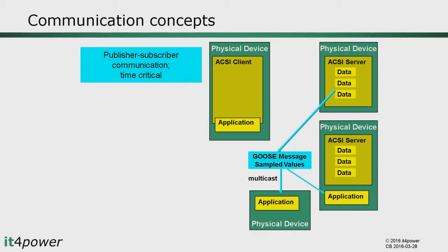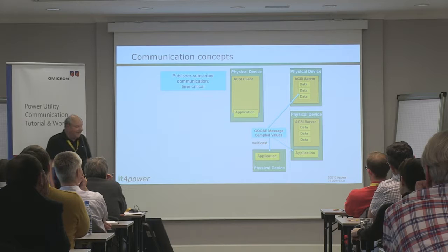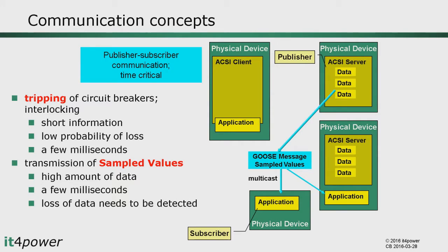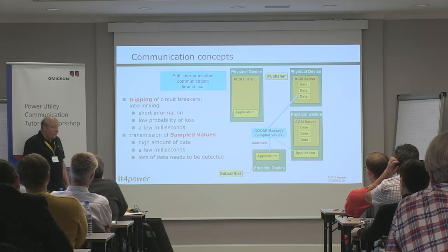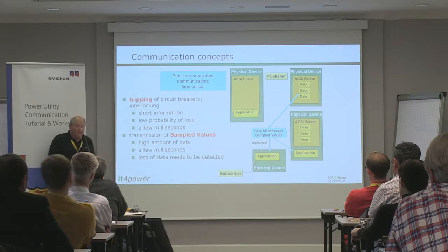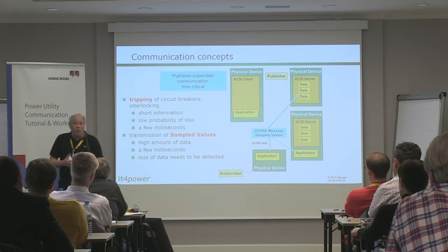For time-critical applications, 61850 uses a second set of communication concepts called publisher-subscriber communication. The concept is that a publisher sends data to subscribers who are interested in receiving it. GOOSE messaging and sampled value transmission are the two key services in this area. This is used for everything time-critical in a substation, as well as for peer-to-peer communication between bay-level devices — for example, tripping of circuit breakers, interlocking, and protection schemes.